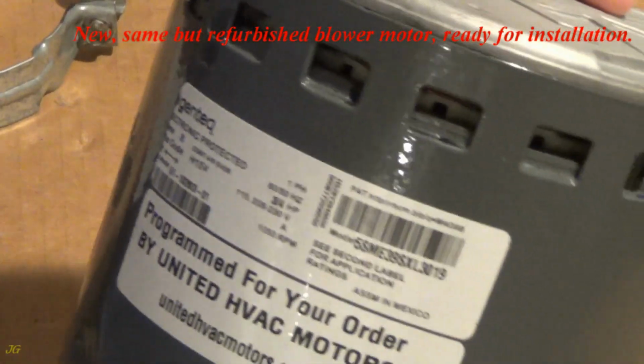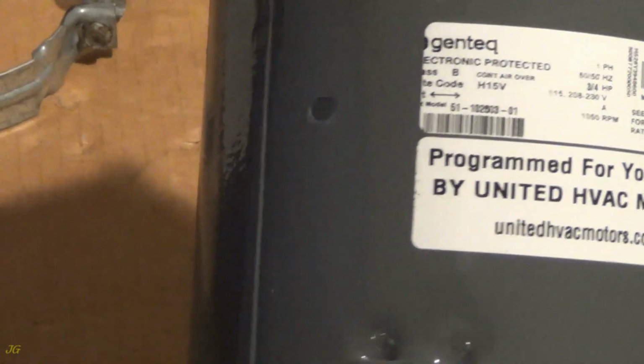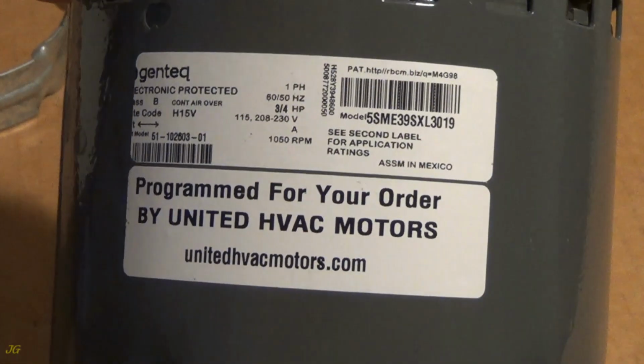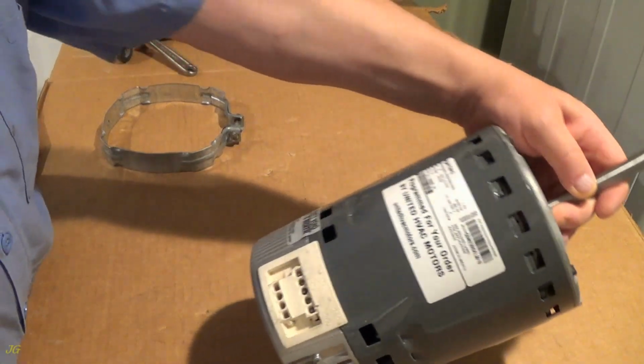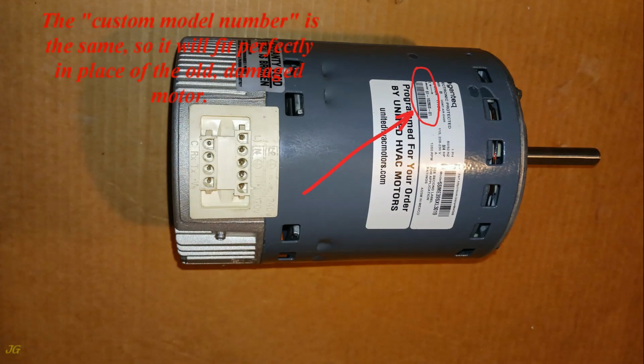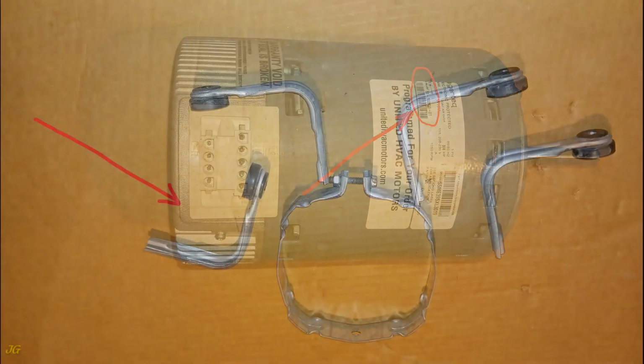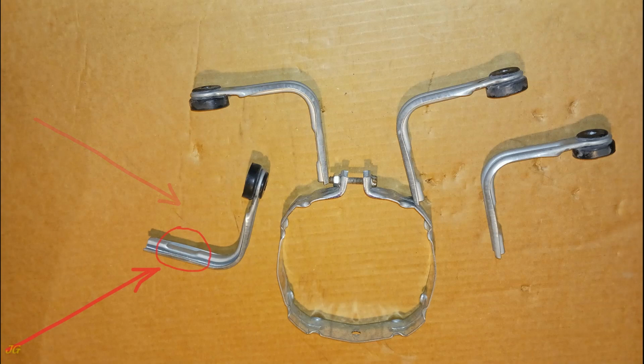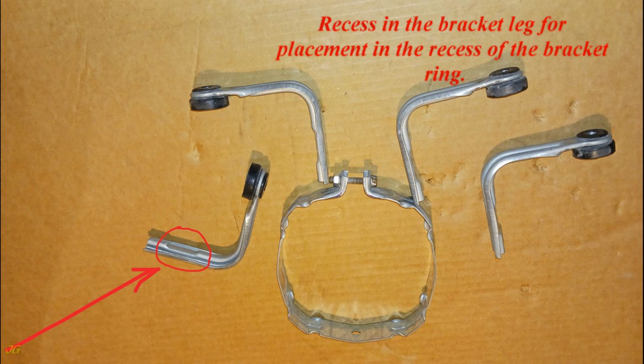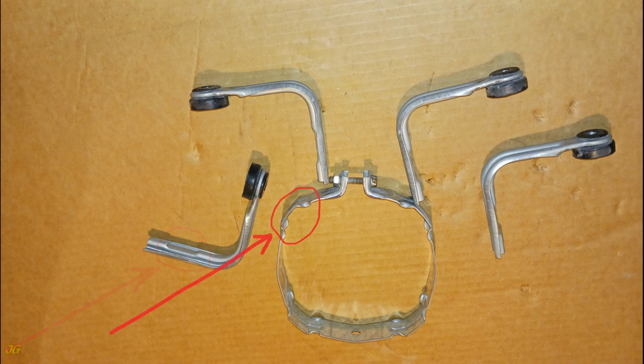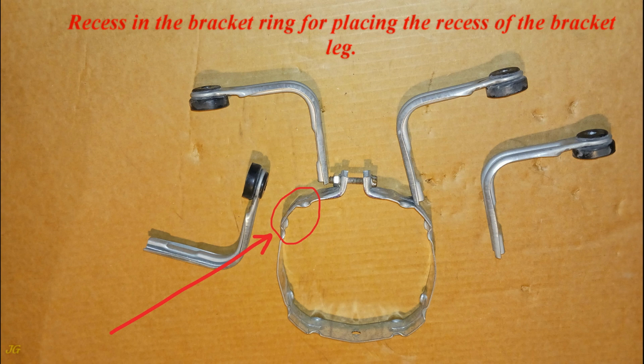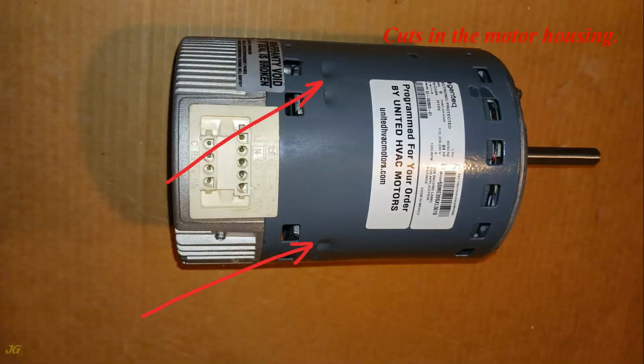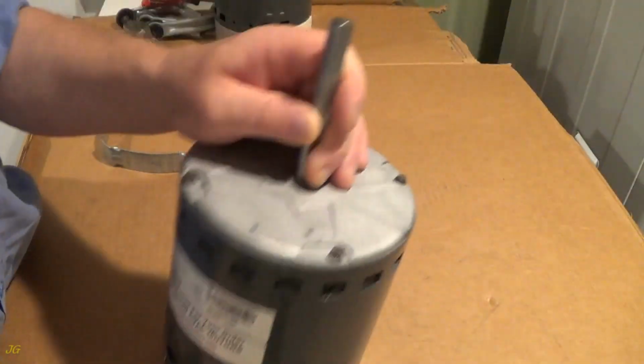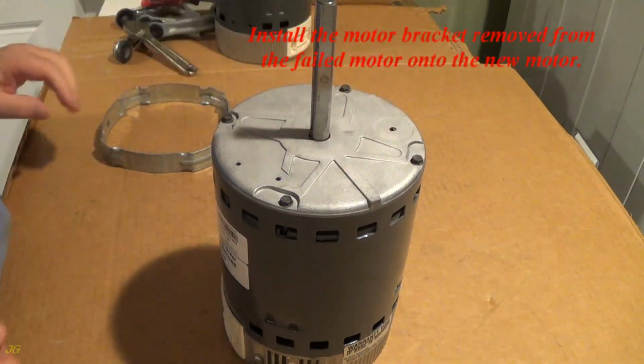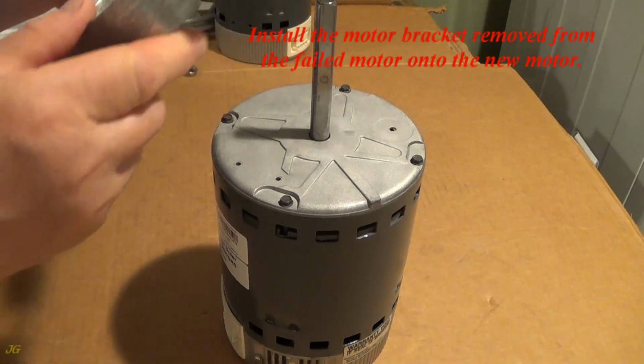New, same but refurbished blower motor, ready for installation. The custom model number is the same, so it will fit perfectly in place of the old, damaged motor. Blower motor bracket. Recess in the bracket leg for placement in the recess of the bracket ring. Recess in the bracket ring for placing the recess of the bracket leg. Cuts in the motor housing. Install the motor bracket removed from the failed motor onto the new motor.